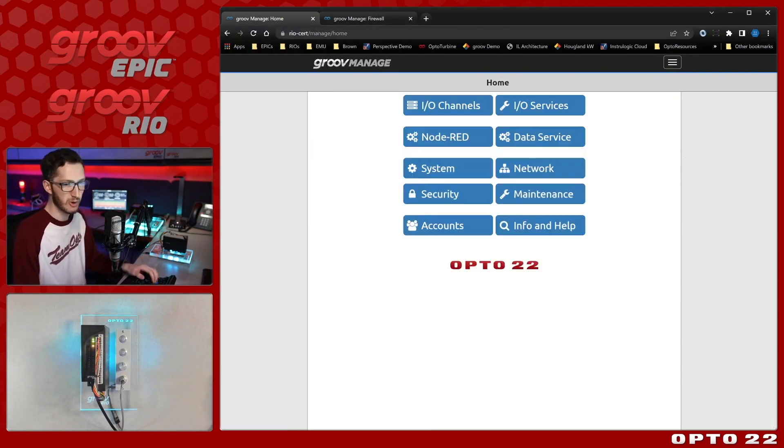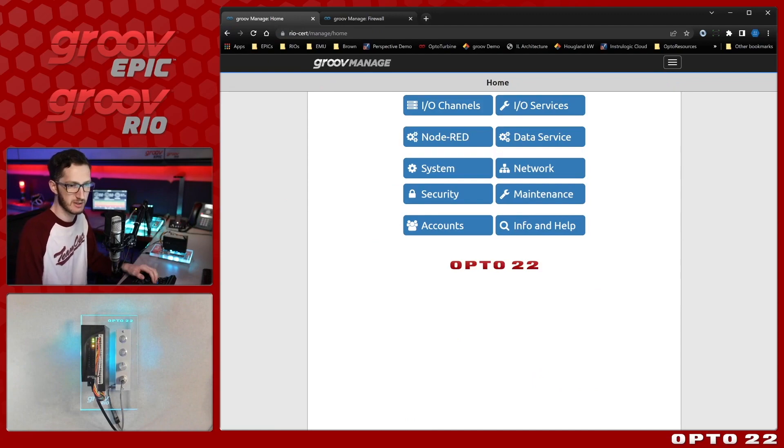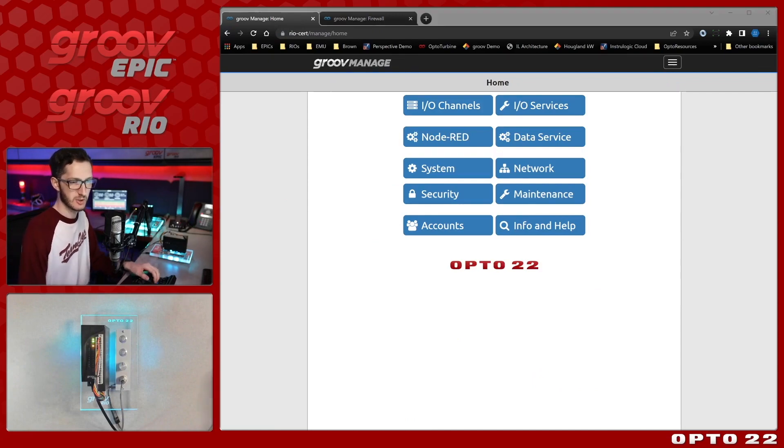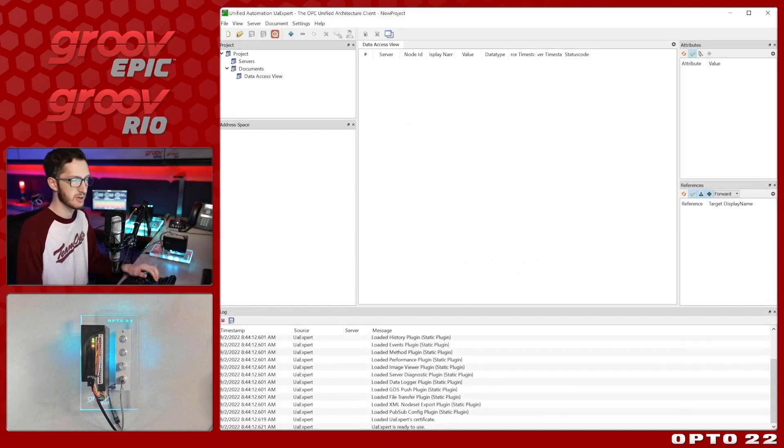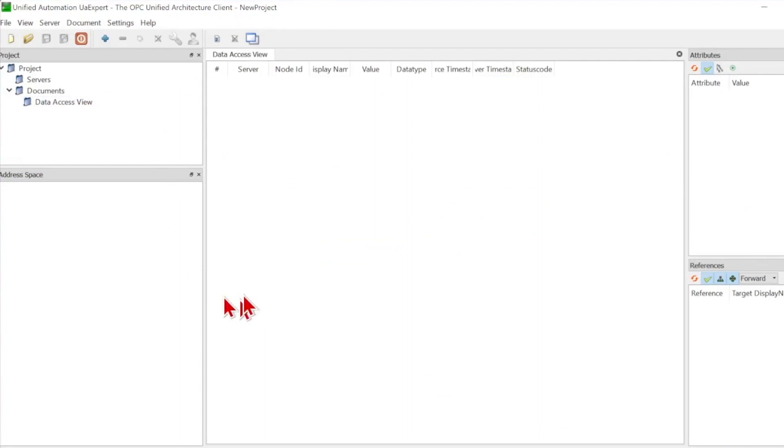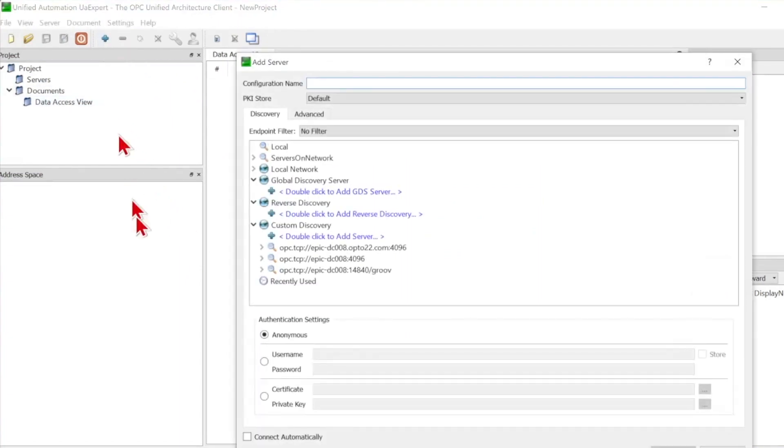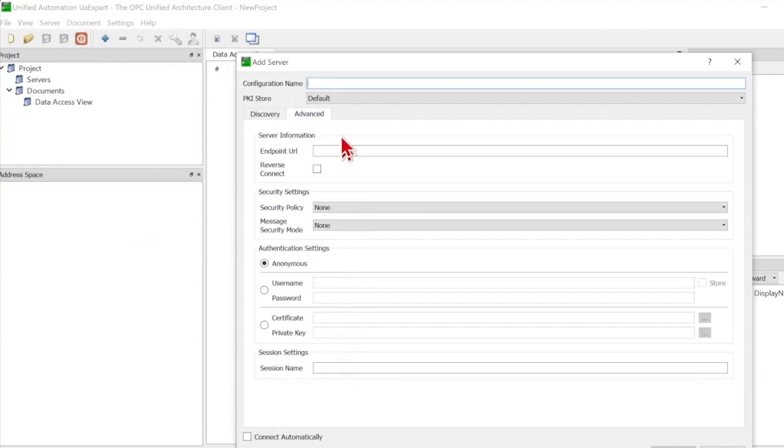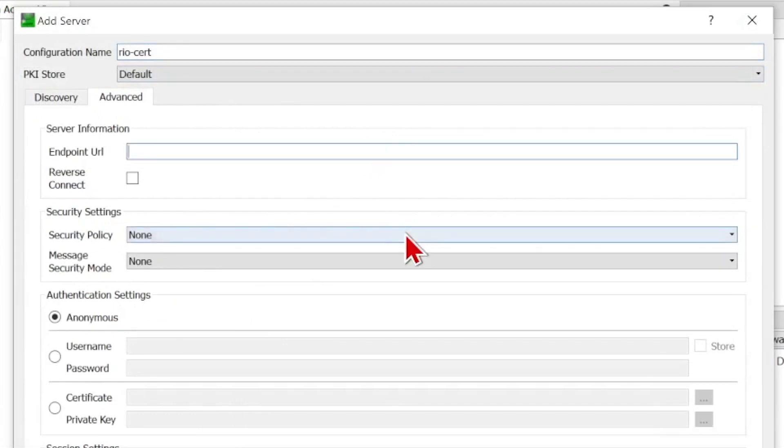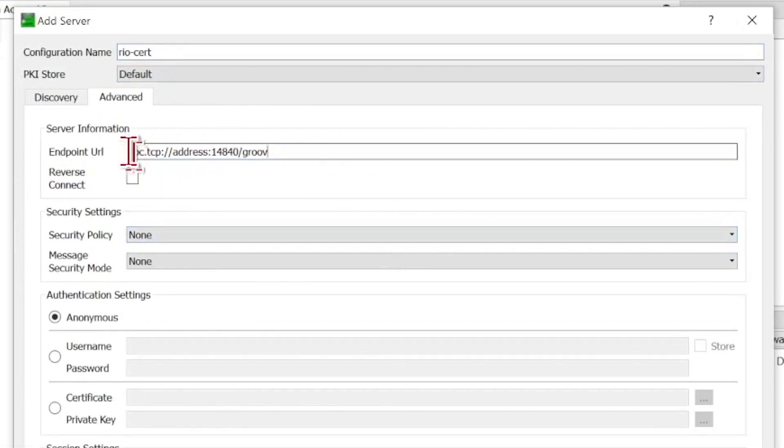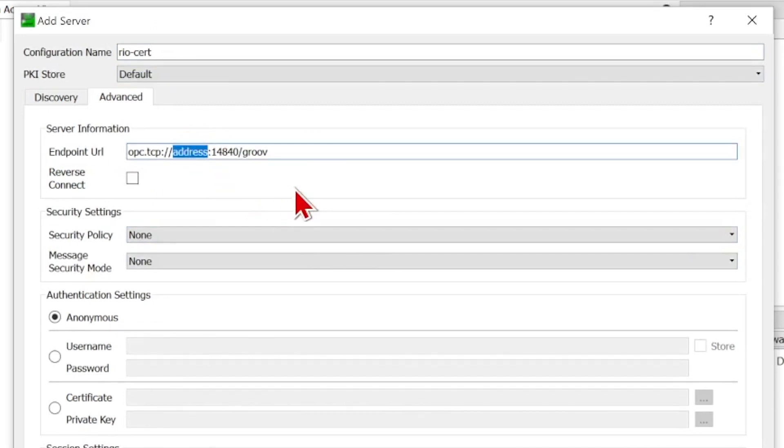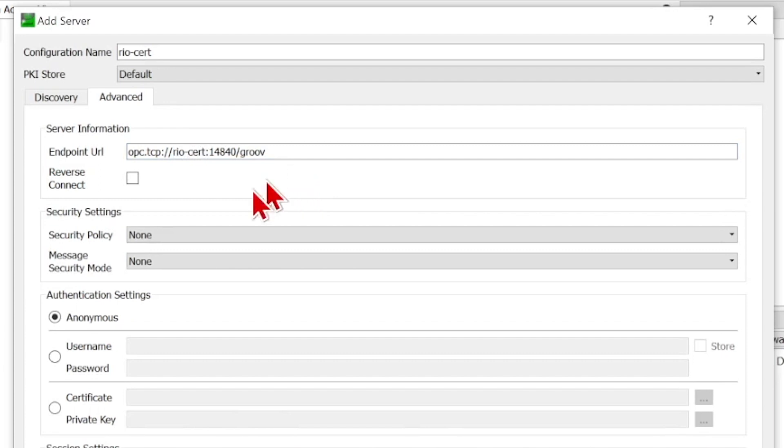So let's bring open my client of choice for this video. It's UAexpert. You can see it's a fresh session here, and we're going to be adding a new server. So I'll come over to advanced so that we can see all the settings available, and I'll give this the configuration name of just the device hostname. Then I'll paste in the endpoint URL, making sure there's no spaces on either side or extra characters. And I will need to replace that generic address with either the IP address or the device hostname. So, I'm going to stick with hostname. Just type in rio-cert, and we're good to go there.